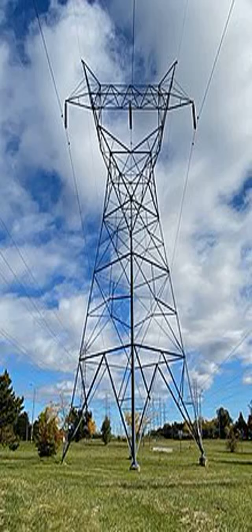Towers used for single-phase AC railway traction lines are similar in construction to those towers used for 110 kV three-phase lines. Steel tube or concrete poles are also often used for these lines. However, railway traction current systems are two-pole AC systems, so traction lines are designed for two conductors. These are usually arranged on one level, whereby each circuit occupies one half of the cross arm.